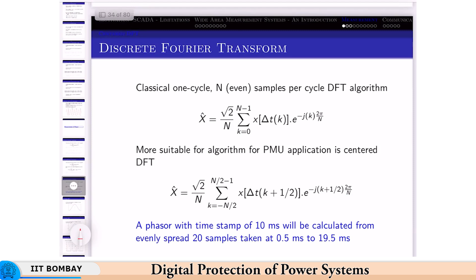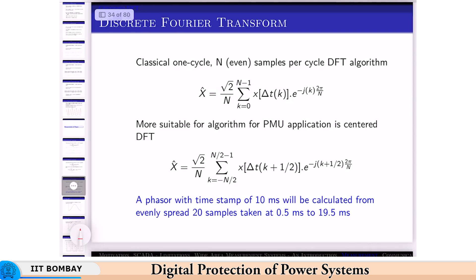So the timestamp of 10 milliseconds is 20 samples from 0.5 to 19.5 milliseconds. Earlier, what we would have done is calculate the phasor with samples 0.5 to 19.5 as a 20 millisecond phasor, but here, because of the centered DFT, it is the 10 millisecond phasor.